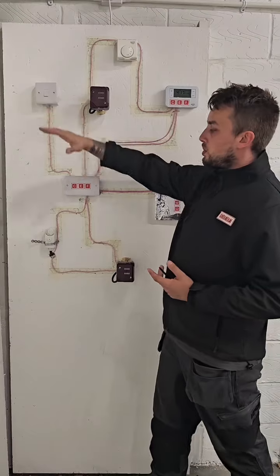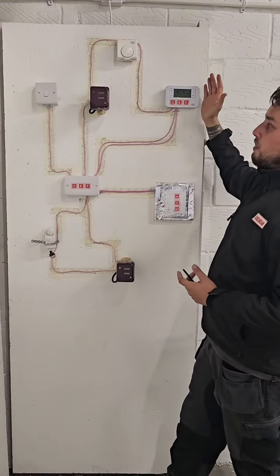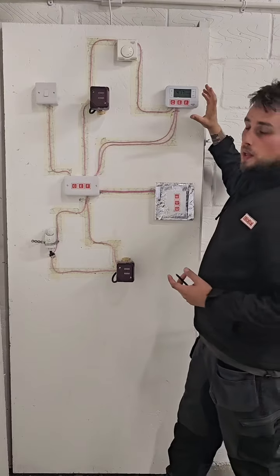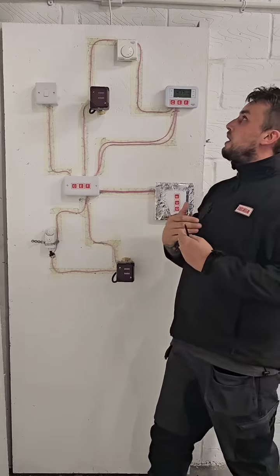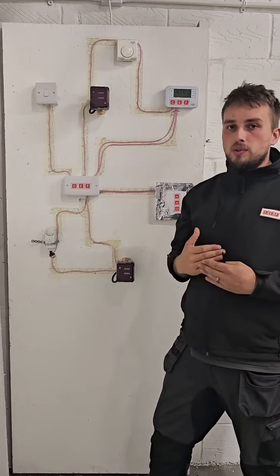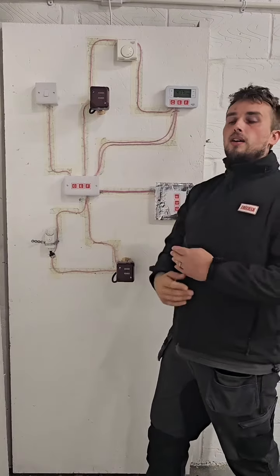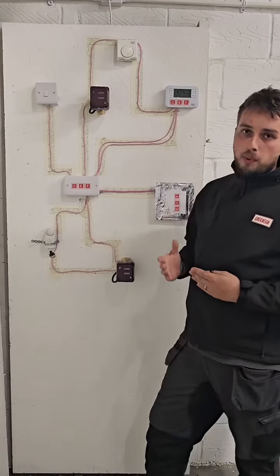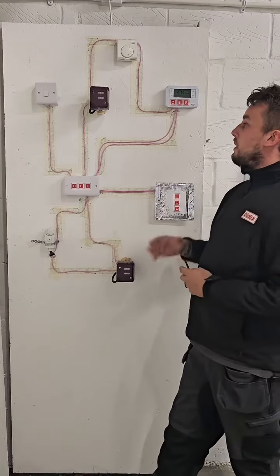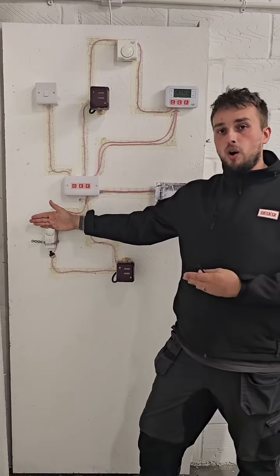Your spur would turn on your power to your wiring centre, which would give power to your programmer. When you call your central heating, that will send power to your room stat. Now, if your room stat is below the required temperature, it will let the power run through to the port valve. When the port valve opens, that will send a signal back to turn on the boiler and turn on the pump. And the same thing would happen if your programmer requests hot water.